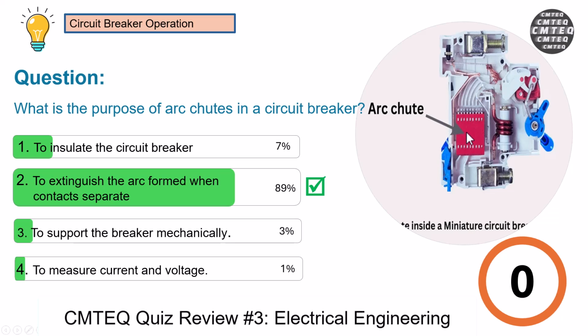The clever design of the arc chute is basically to split the arc, cool it, and lengthen it. By forcing it into smaller sections, the arc quickly loses its energy, and ultimately it will extinguish safely. Because if that doesn't happen, the whole thing can explode. So this is why we've got an arc chute.